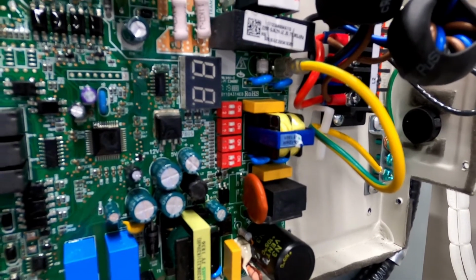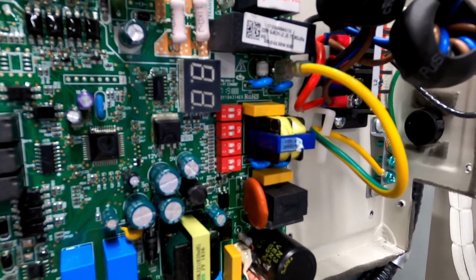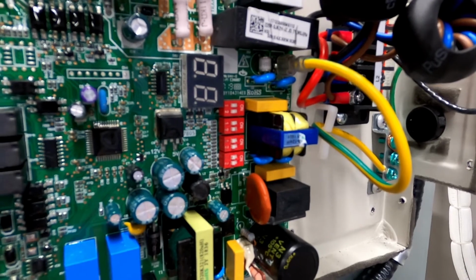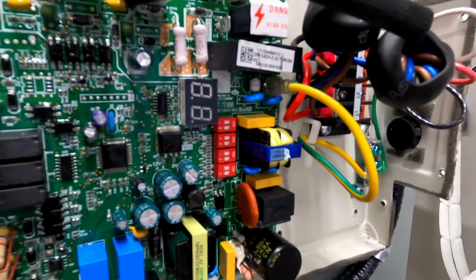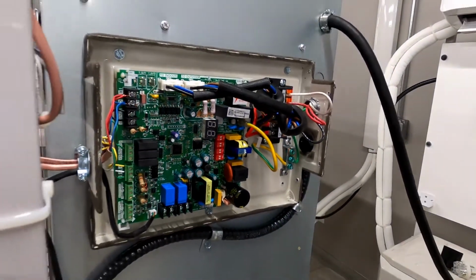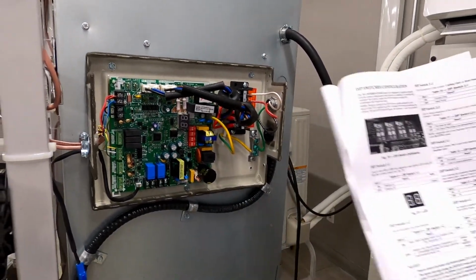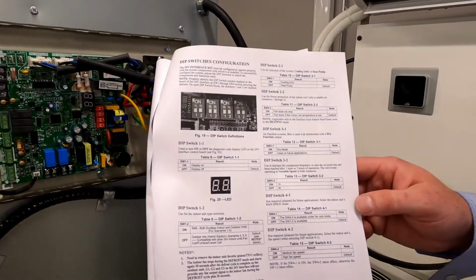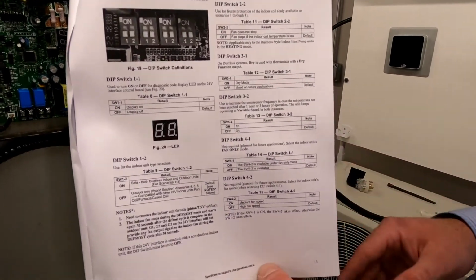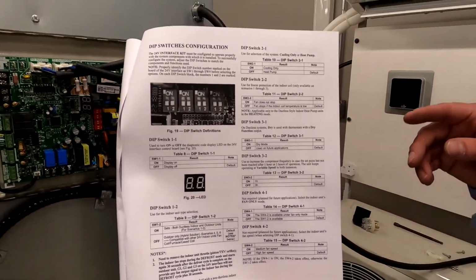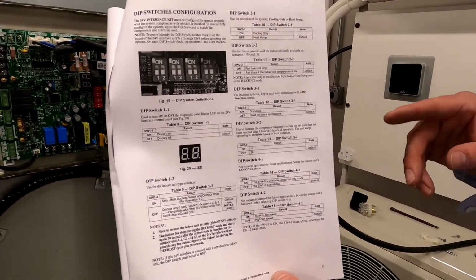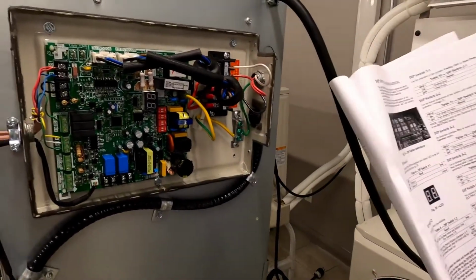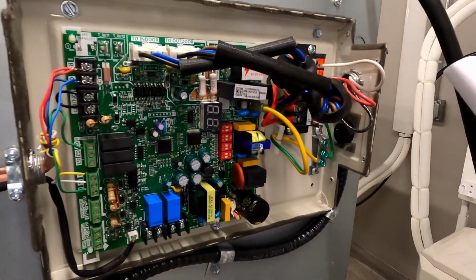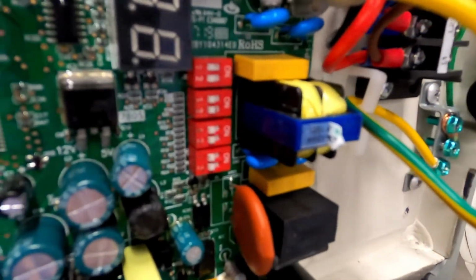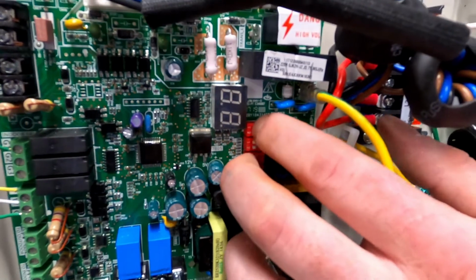All right, now that we have everything else installed and complete, before we power the system up, we need to properly set the dip switches on the 24-volt interface kit so that the system will operate properly with the combination that we have. So we need to turn to the page in the manual that came with the 24-volt interface kit that shows the dip switch settings, and we'll go through and set each one. So SW1-1 by default is off. We're going to turn that on. So that one turns the display on.